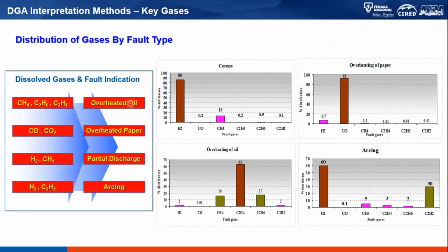Whenever there is overheated oil, there will always be these heating gases generated - methane, ethane, and also ethylene. If paper is overheated, as we saw in the previous slide, it will decompose and release carbon monoxide and carbon dioxide. If we have partial discharge inside of our winding, that will cause the oil to break down and generate hydrogen and methane. And if there is arcing, it will generate hydrogen and acetylene.